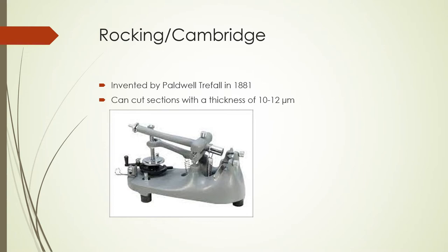Starting off with the rocking or Cambridge microtome — it was invented by Paldwell Trefall in 1881 and can cut sections with a thickness of 10 to 12 microns. As the name suggests, it cuts tissues in a rocking motion. Looking at the picture, it kind of looks like a mini seesaw with spring-load balances on one side, cutting tissues in a rocking motion back and forth, up and down.